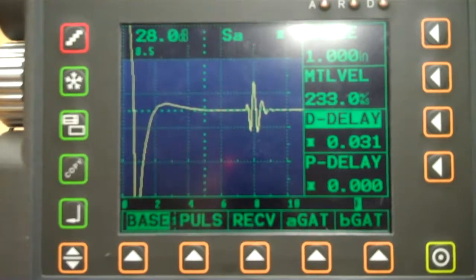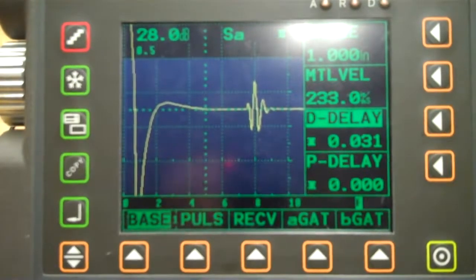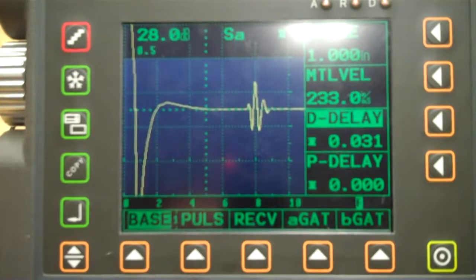Alright, good afternoon. Just wanted to do a little bit of work here with the scope again. Wanted to show you compressional beam thickness testing and some of the stuff that goes along with that. Then we're going to look at dual element thickness testing. Then we're going to look at a delay line. Then we're going to calibrate up to a shear wave. And then we're going to look at that calibration on a DSC block. Those are kind of the videos that we're looking at this week.